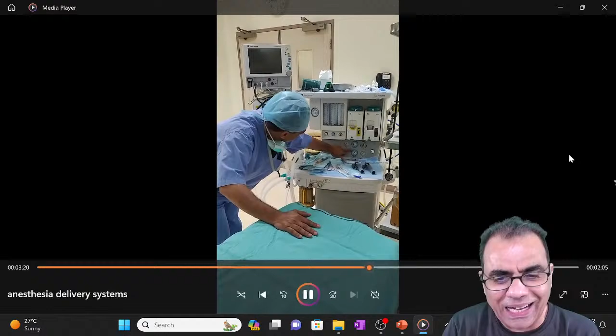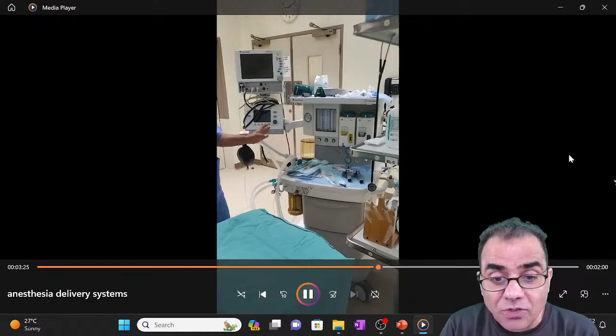These are the gauges which tell you how much pressure is there in the cylinder and how much pressure is there in the central supply. And if the pressure falls, the machine starts alarming also. So we can know that there is a decrease in oxygen or a decrease in nitrous oxide. And this is the rotameter I told you. You can clearly see these are the rotameter tubes, flow meter tubes.